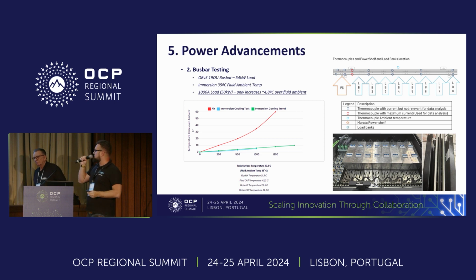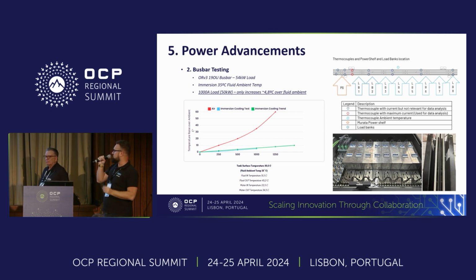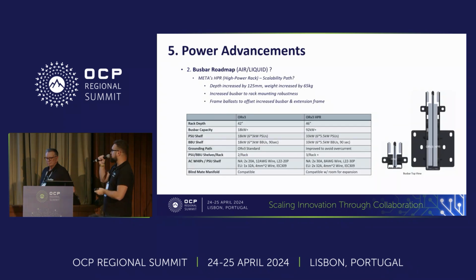What happened is that in immersion, bringing 1,000 amps of load, so 50 kilowatts, didn't even increase the temperature by 5 Celsius in the same ambient conditions. In air, you can see the trend in the red line - at just 1,000 amps we're already at a 35 Celsius temperature increase. So probably, as Meta was presenting this morning, solutions involve going to bigger busbars with more copper to reduce the temperature in air environments.